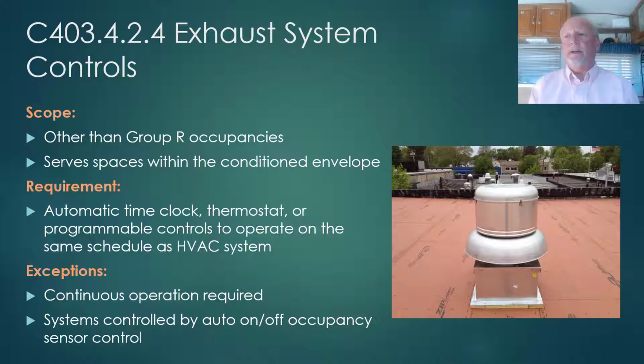And so that can be done with an independent time clock. It could be a programmable controller. It can be connected to a thermostat, or through some sort of centralized building management system. Some exceptions to that are systems requiring continuous operation. Obviously, you wouldn't want to shut off the exhaust fan in that. And then also systems controlled by occupancy sensors. So the individual exhaust fan in the restroom, if it's shut off automatically, doesn't need to have a time clock control. As long as you've got that occupancy sensor control, you're fine.